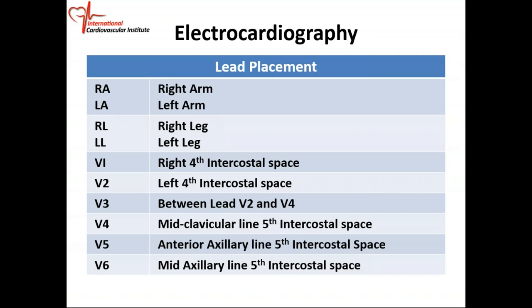We're going to put these electrodes at different positions, and you have to know the correct position. We put electrodes on the right arm — either the forearm or the shoulder area — and on the left arm similarly. Then the right leg, which can go on the leg itself or in the right groin or lower abdominal area. And then the left leg, similarly on the leg or the left groin. These are what we call limb leads.